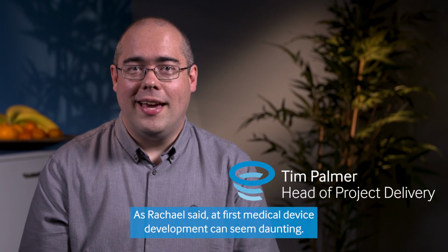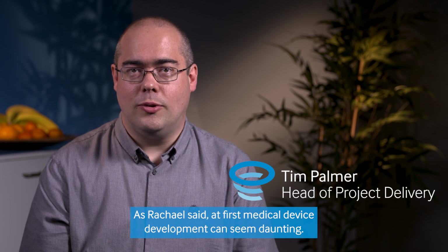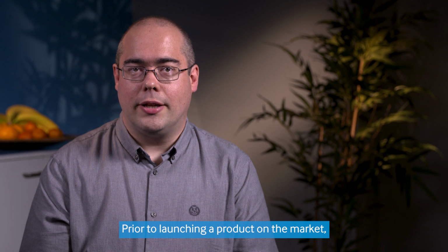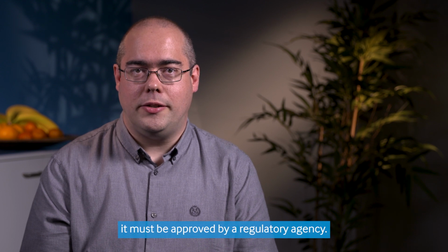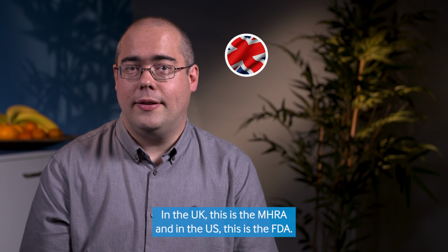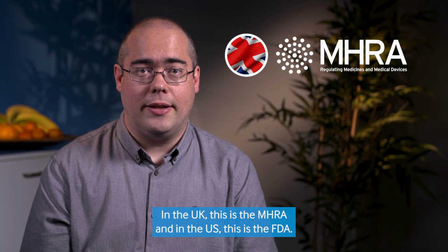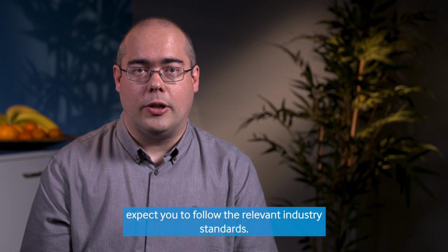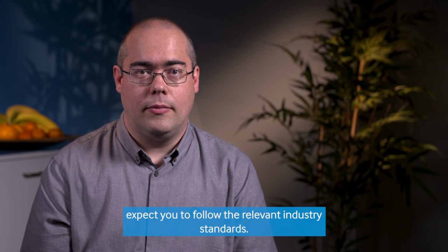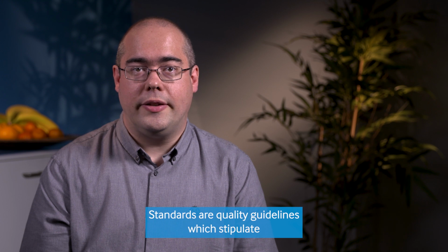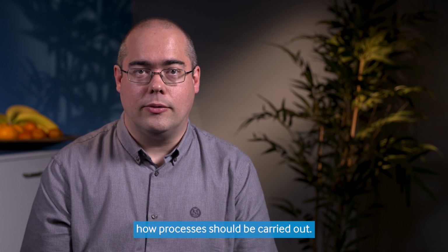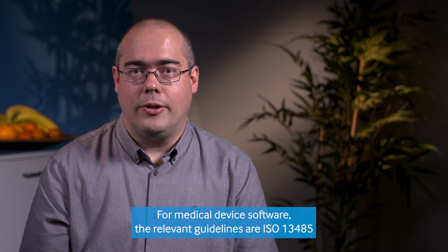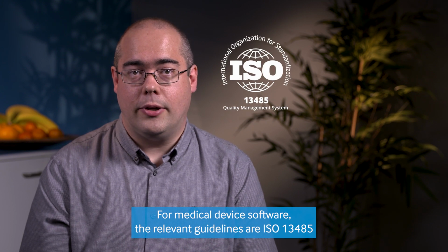As Rachel said, at first medical device development can seem daunting, so let's demystify it. Prior to launching a product on the market, it must be approved by a regulatory agency. In the UK, this is the MHRA, and in the US, this is the FDA. Regulatory agencies will expect you to follow relevant industry standards. Standards are quality guidelines which stipulate how processes should be carried out. For medical device software, the relevant guidelines are ISO 13485 and IEC 62304.